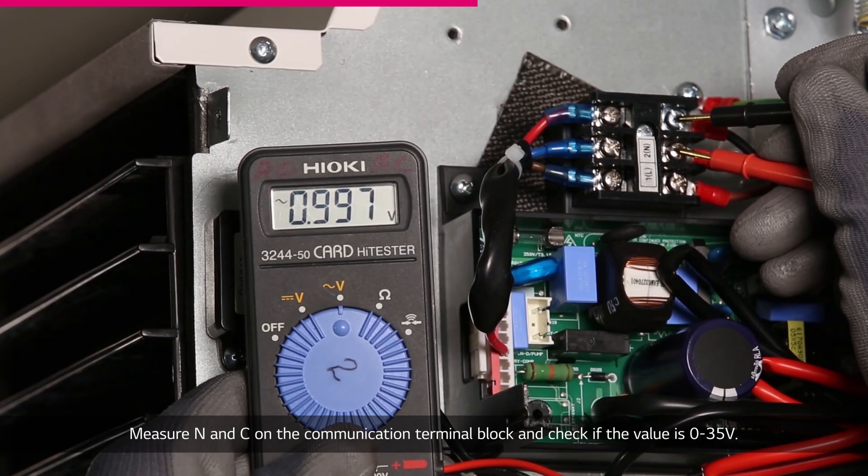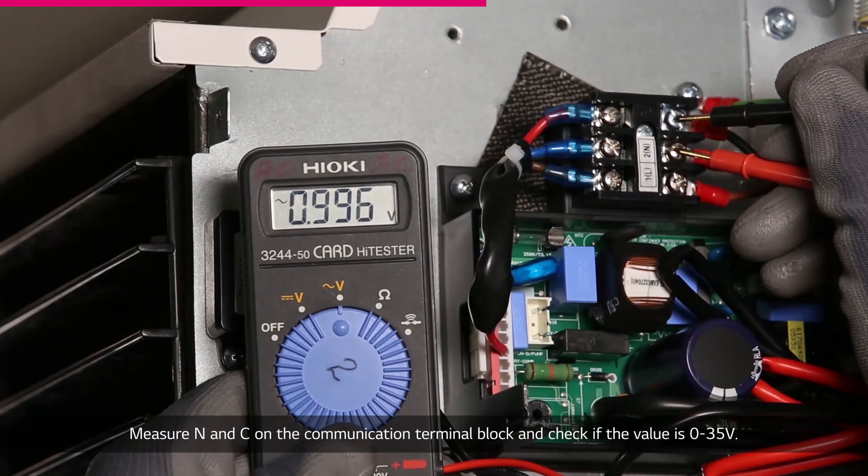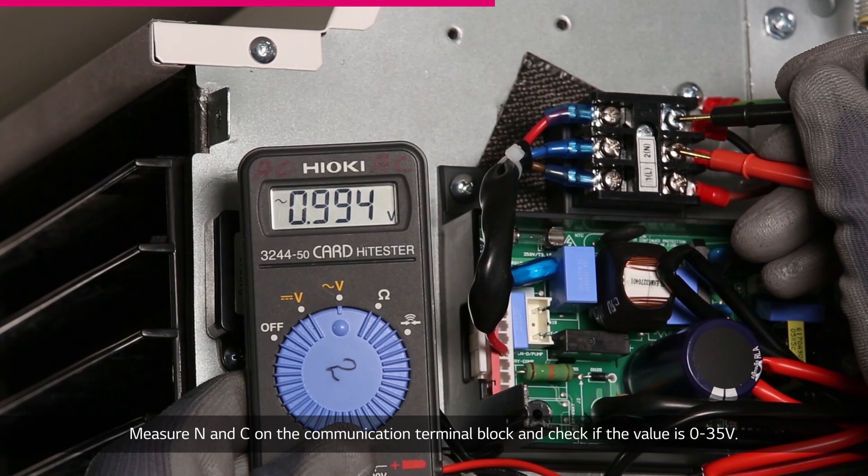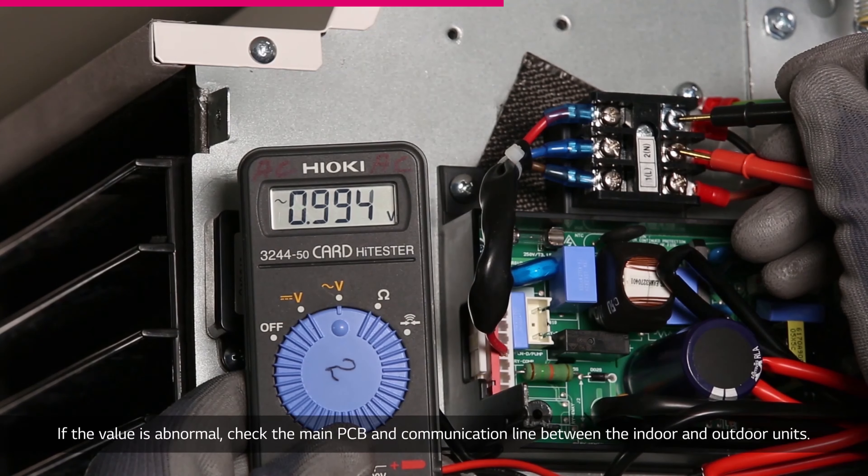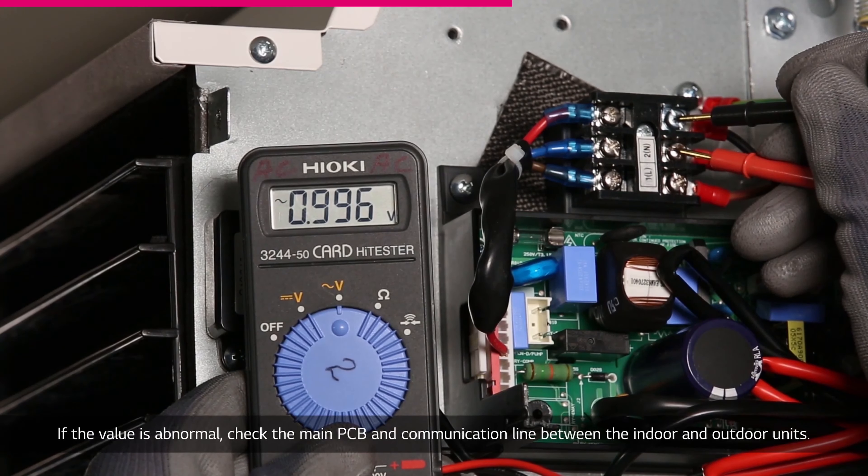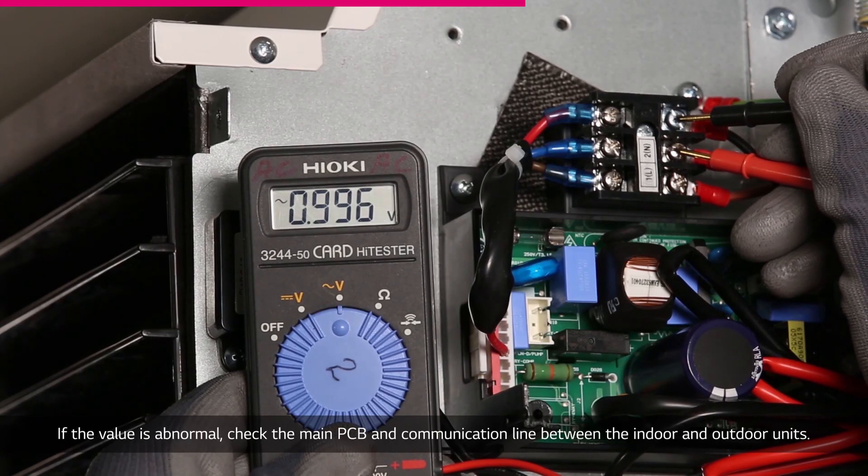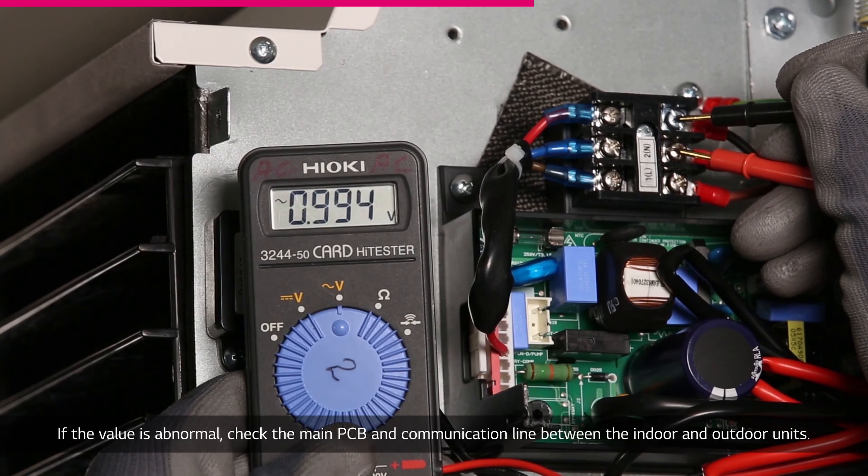Measure N and C on the communication terminal block and check if the value is 0 to 35 volts. If the value is abnormal, check the main PCB and communication line between the indoor and outdoor units.